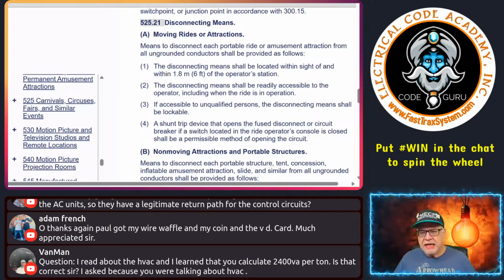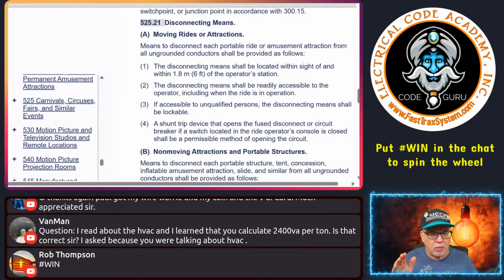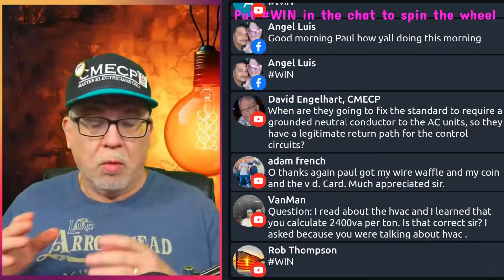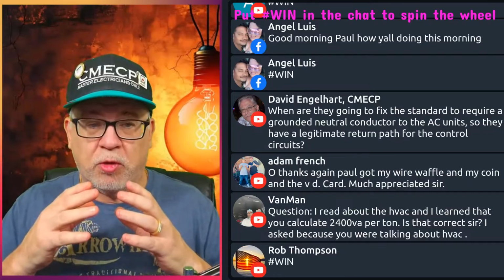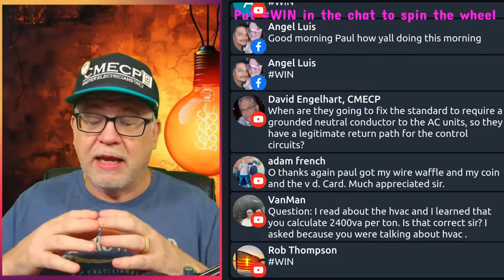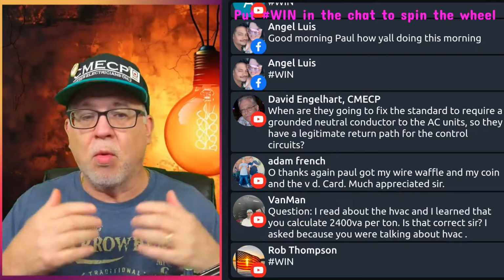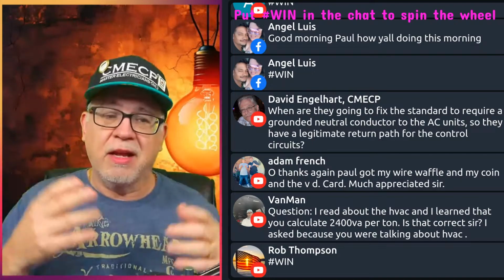Now the next one, the world of EVSE when it comes to GFCI protection. I believe, even though the CMPs and all came through with this stuff, ultimately what I think is going to happen is the CMP's proposal failed, and it's going to go back to the code panel anyway. The code panel is going to vote their intentions, and their intention is that they want permanently installed EVSEs, as well as cord and plug connected EVSEs, to require GFCI protection. Now here's the thing: when it's a receptacle, it's required whether it's 150 volts or less to ground, that'd be your typical 120, 240 volt, or it goes to over 150 volts to ground. Those would be more like the 208 volt ones, or more commercial applications rather than residential, okay?